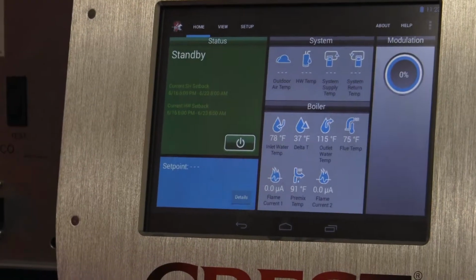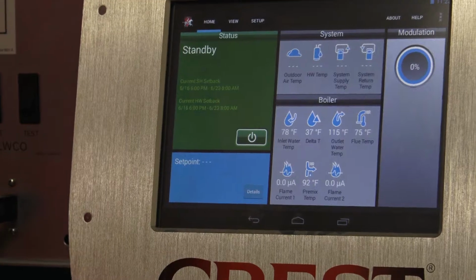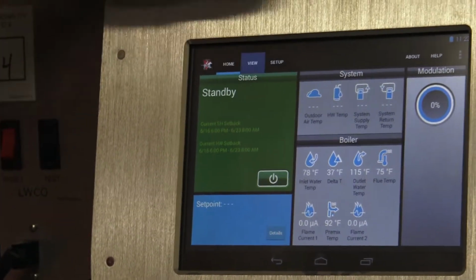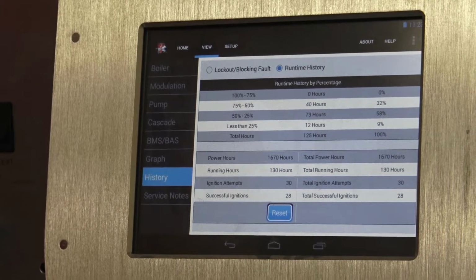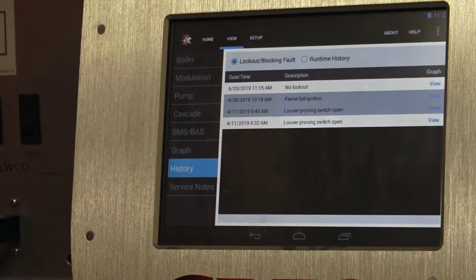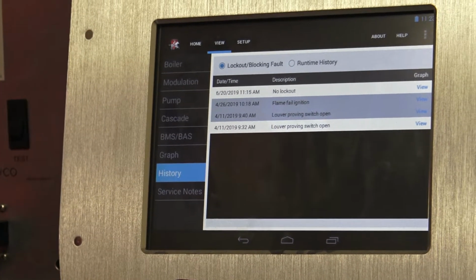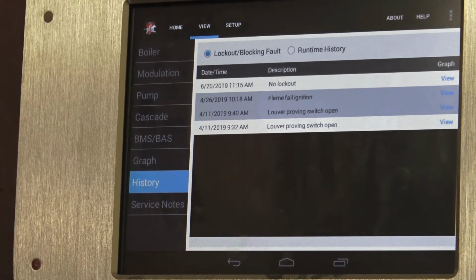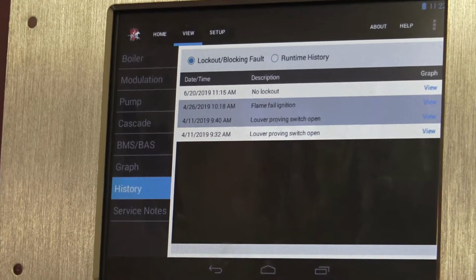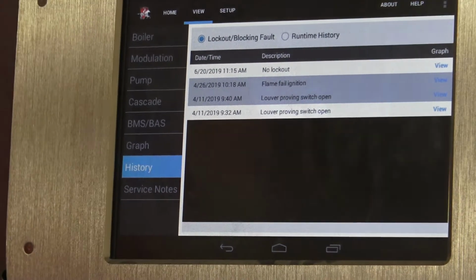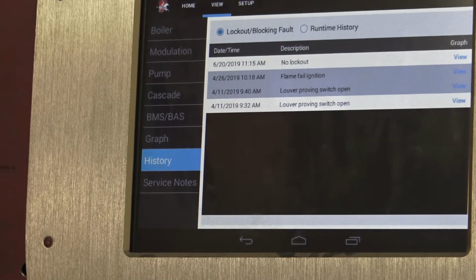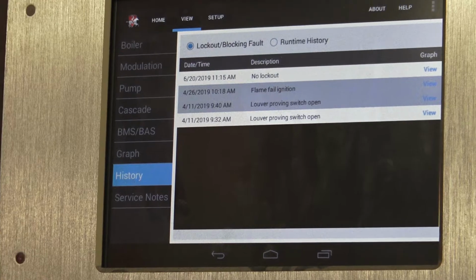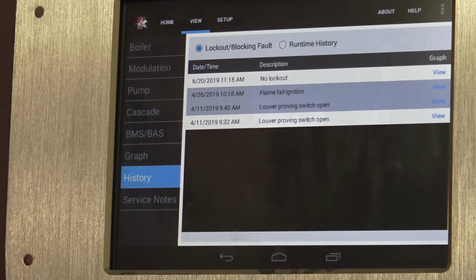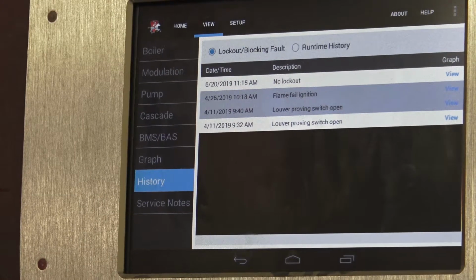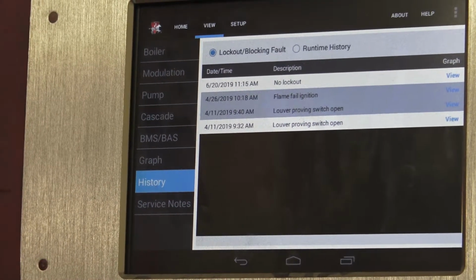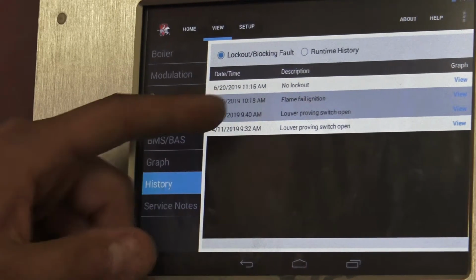So if we do have, let's say, some failures or some flame issues, what's going on? We can go to this view screen, and we can see the history. So right now I know that this boiler didn't fire for a month or 2, and they came to start it, and it failed on ignition. Well, you've had stagnant gas sitting in the pipe between here and here for 2.5, 3 months. He came up, he hit the reset button on the screen, and it fired right back up, and that's just from not firing for 3 months. So you can see that right there.